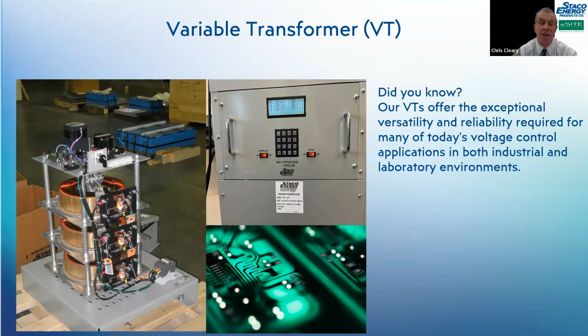Then we've got a little bit more of an advanced look there on the right-hand side, what looks like a keypad and a screen. That is our microprocessor controller that allows for communication directly to the unit itself. So you can program in an output voltage via the keypad, or you can use serial communication capability and have that unit adjust the output voltage via, say, a PLC or an HMI or a computer, anything like that in terms of how you want to do it. And then that output will be regulated so that you can precisely test your units to a plus or minus 1 volt, possibly even better than that. So again, they're really kind of simple units, you have one input voltage and then a varying output voltage.